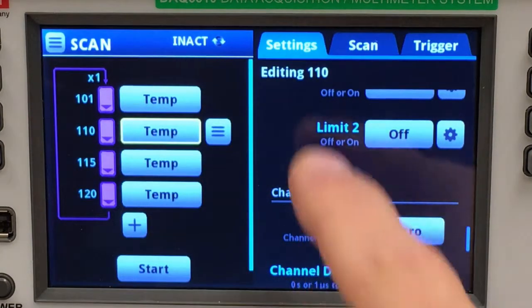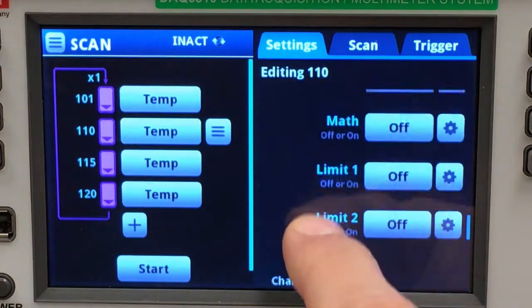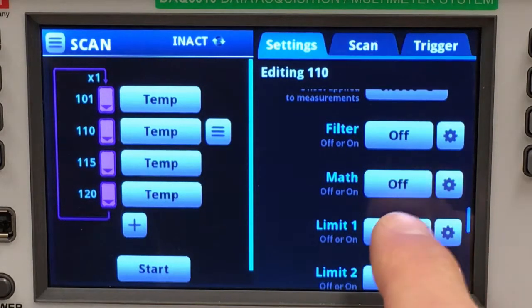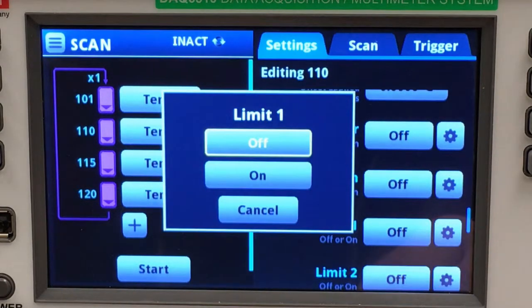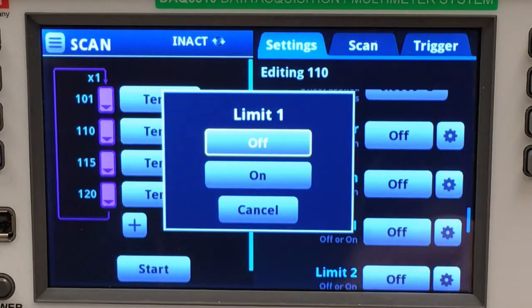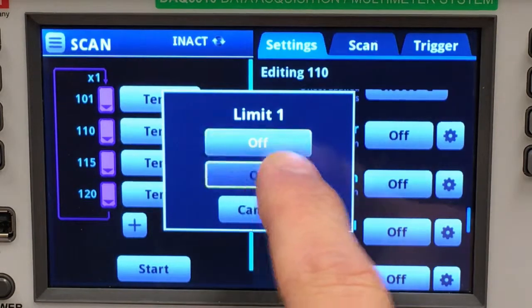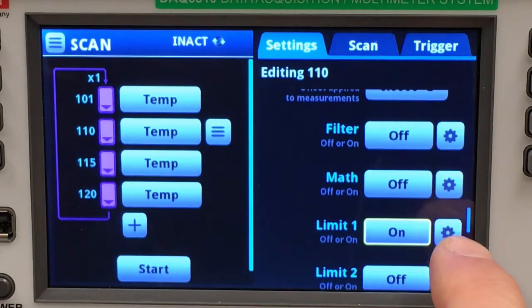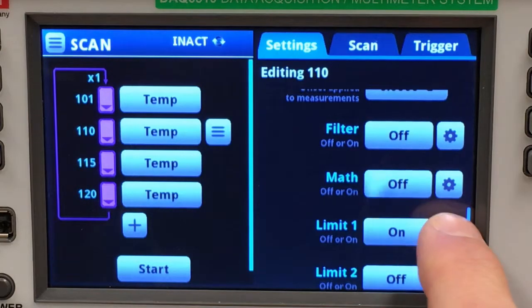Channel 110 is monitoring a microprocessor and it has a tendency to get hot. Let's provide ourselves a notification if something goes wrong and we hit that condition, so I will establish a limit.